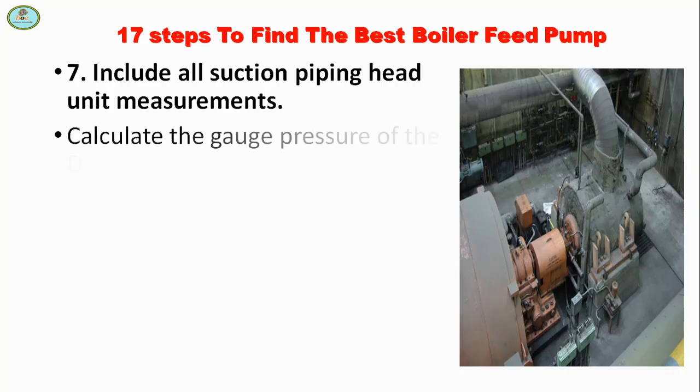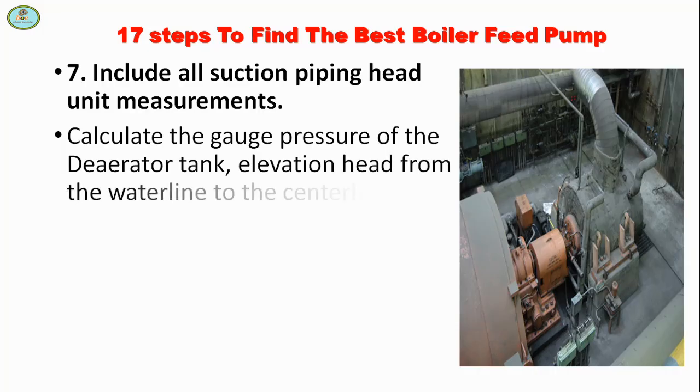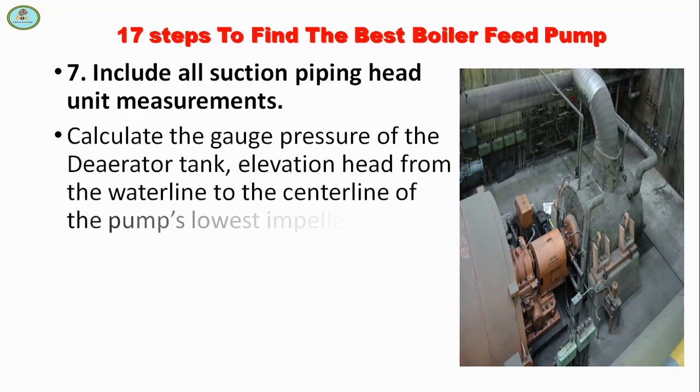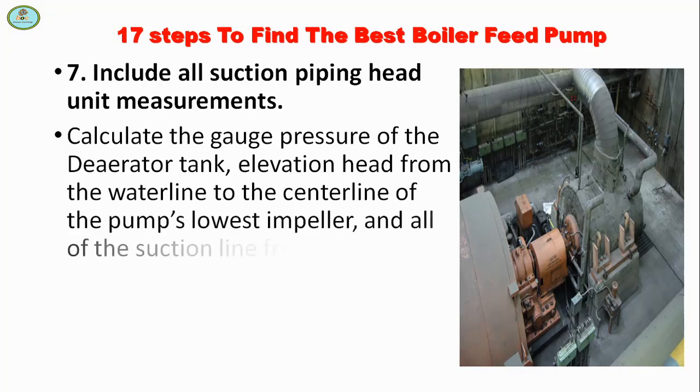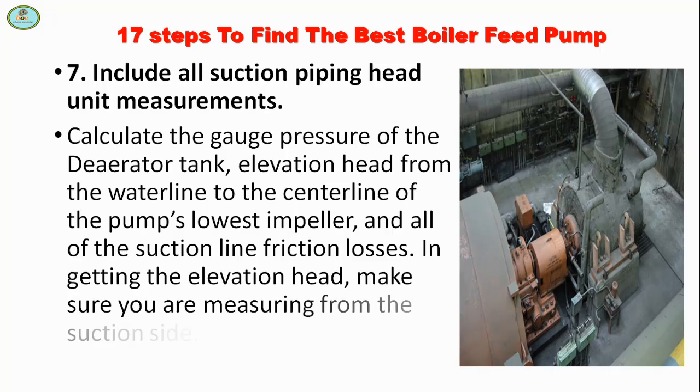Calculate the gauge pressure of the deaerator tank, elevation head from the water line to the centerline of the pump's lowest impeller, and all of the suction line friction losses. In getting the elevation head, make sure you are measuring from the suction side.